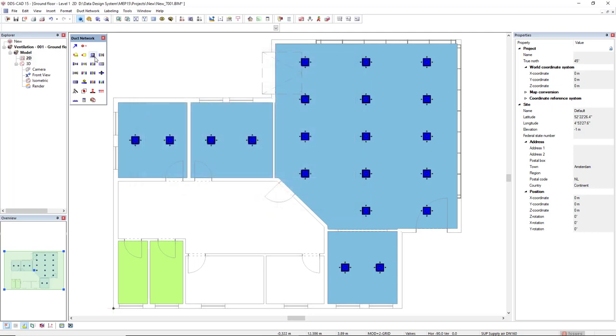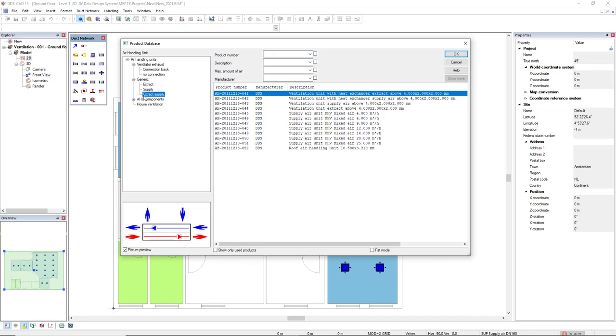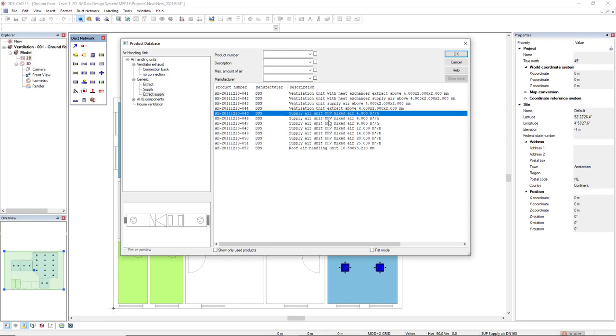If we access now the air handling unit function, I will access the generic filter and then extract supply subfilter. Here we see some generic air handling units in which we see the maximum volume flow they can supply. Like in this case, this one is the maximum volume flow of 4,000 cubic meters per hour. This is totally fine for the zone.